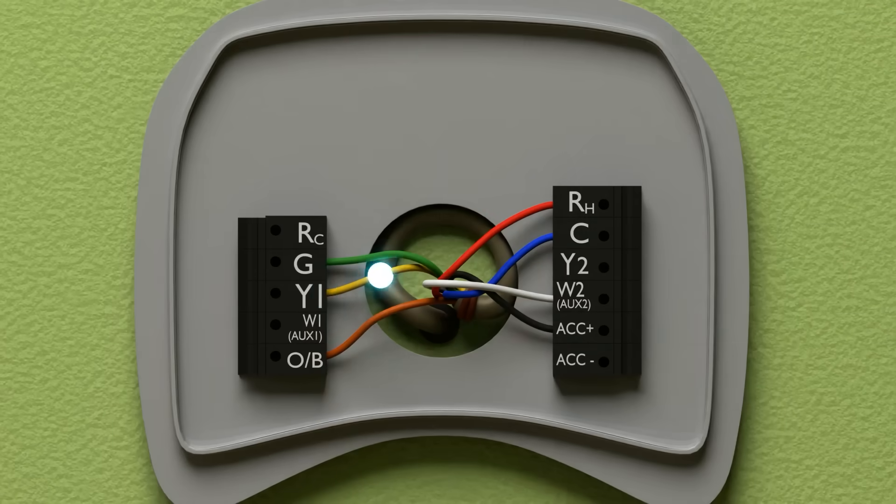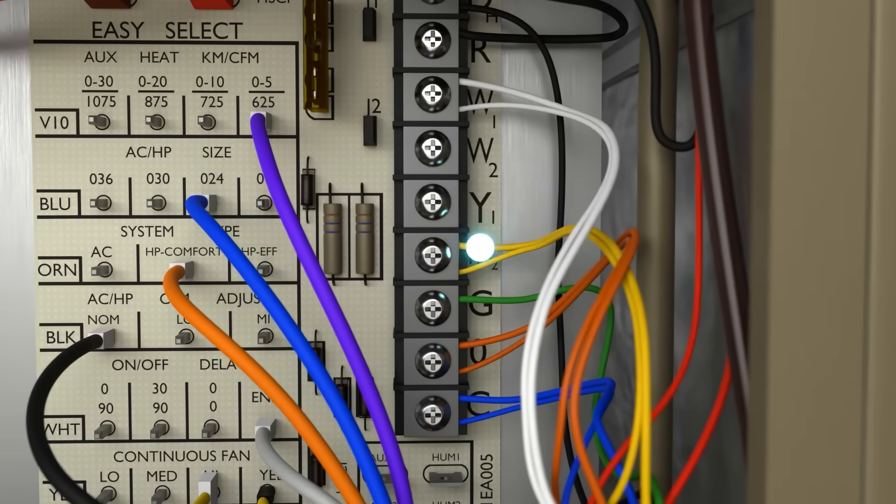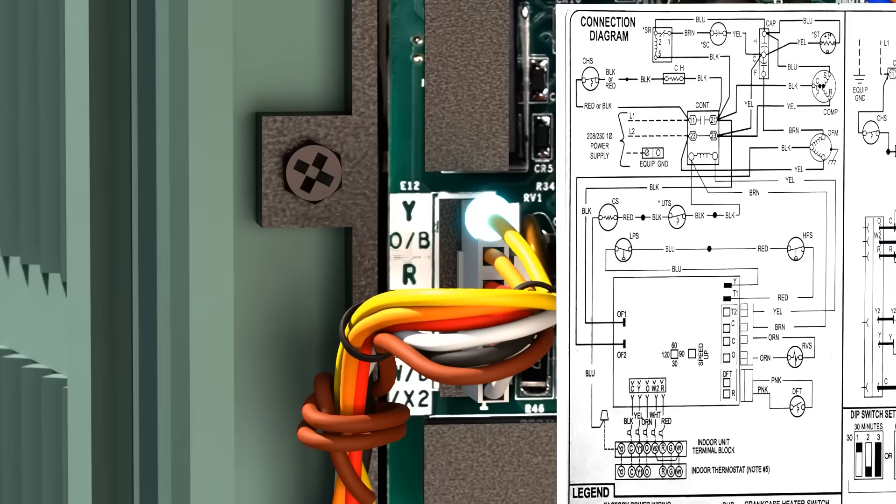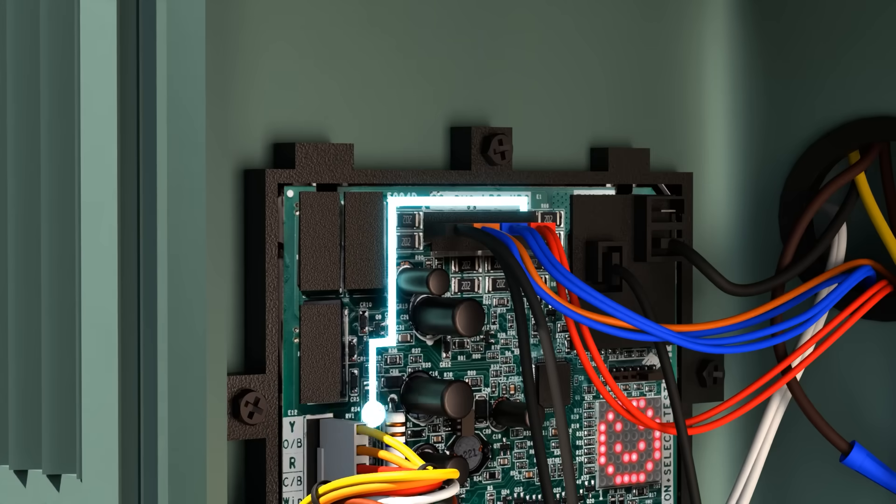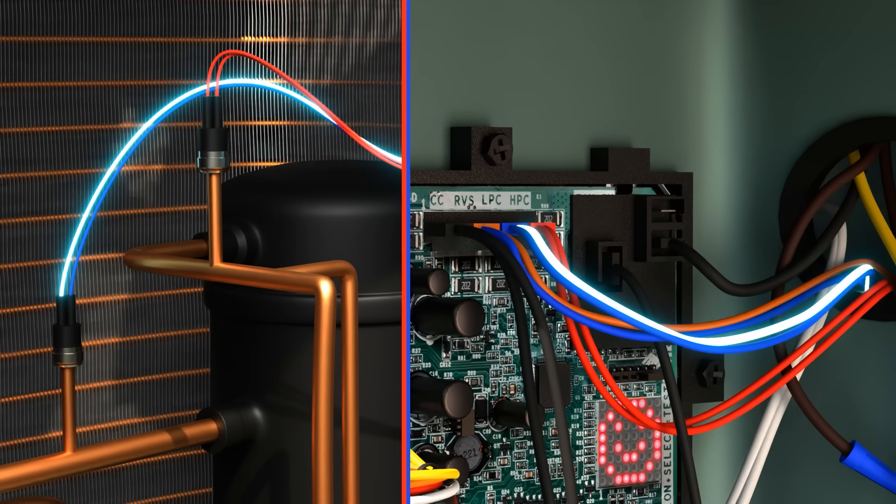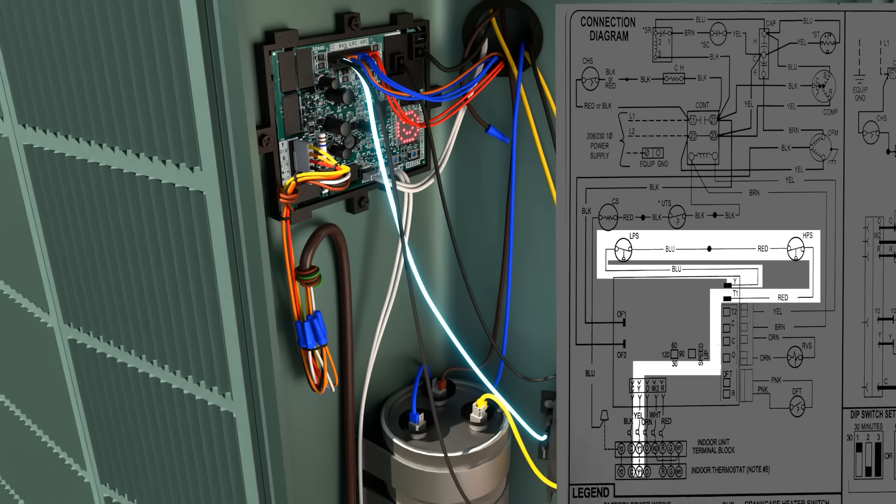The Y circuit goes into the terminal block, which acts as a junction point, and then goes out to bring on the contactor. Y or yellow is used to energize the contactor coil, which pulls the contactor in and allows the condenser fan and the compressor to run. Here we show the Y circuit going in and out of our high pressure switch and low pressure switches before it goes to our contactor coil, as shown in the diagram. If either of these switches open, it won't allow the system to run.